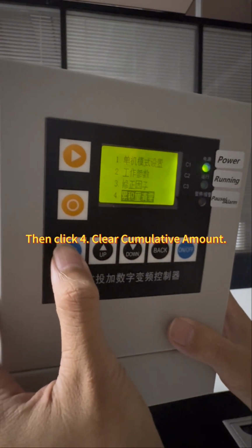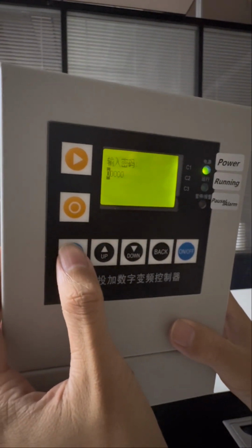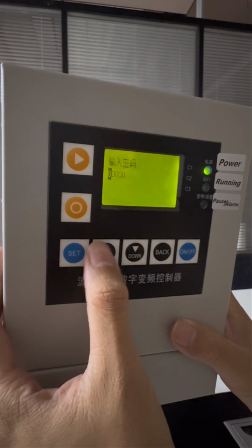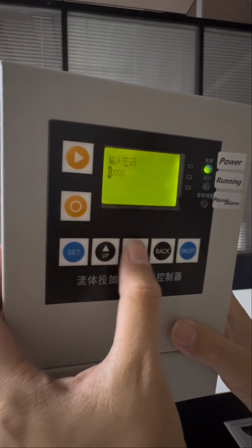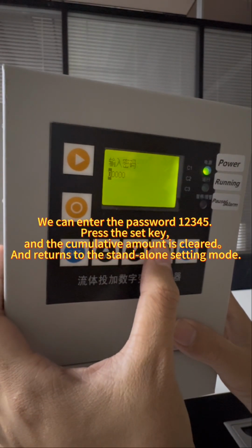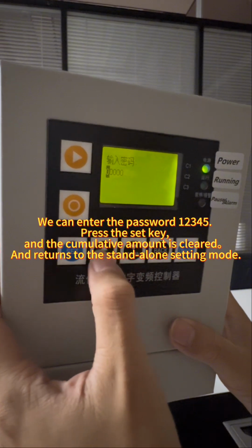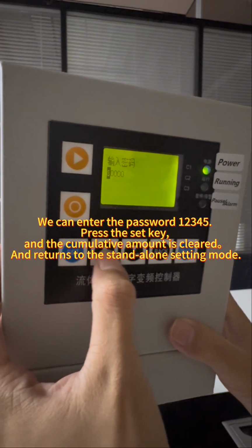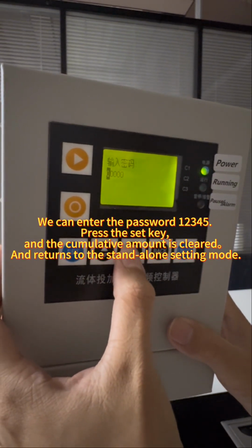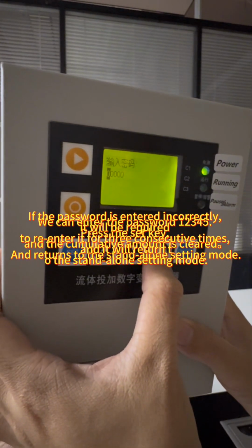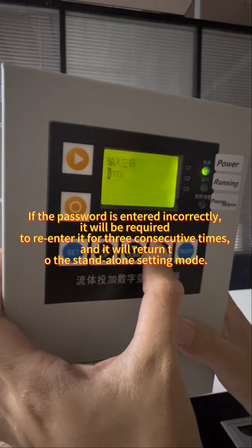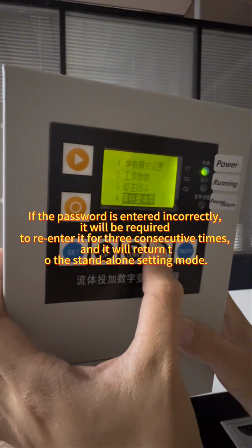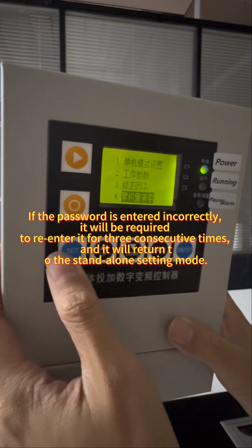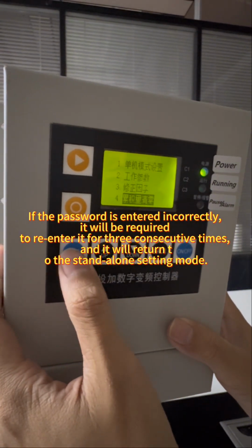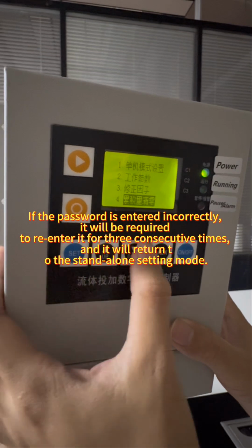Then click Clear Cumulative Amount. We can enter the password 12345, press the Set key, and the cumulative amount is cleared and returns to the standalone setting mode. If the password is entered incorrectly, it will be required to re-enter it; after 3 consecutive incorrect entries, it will return to the standalone setting mode.